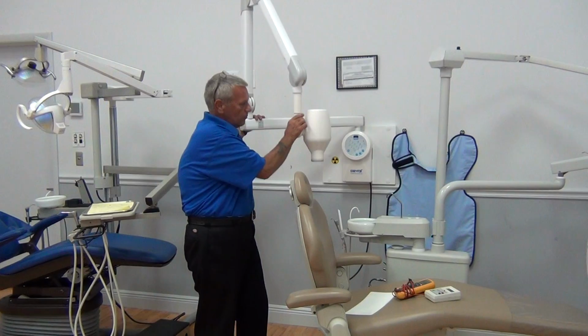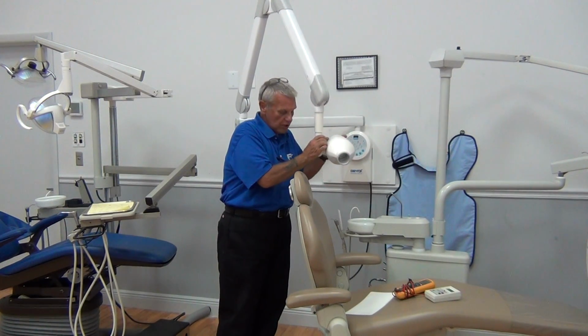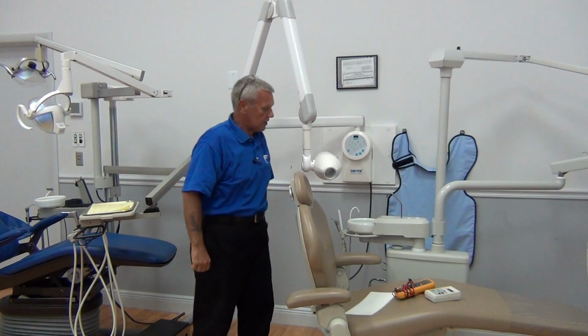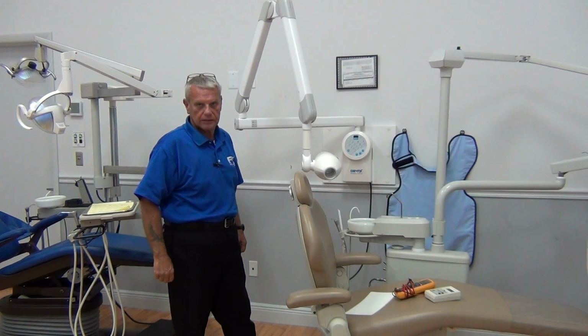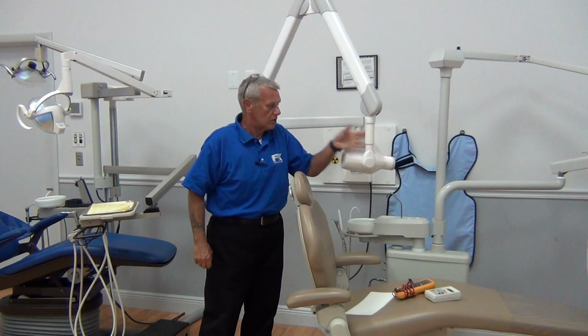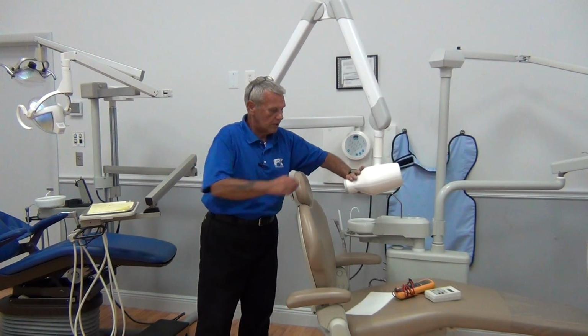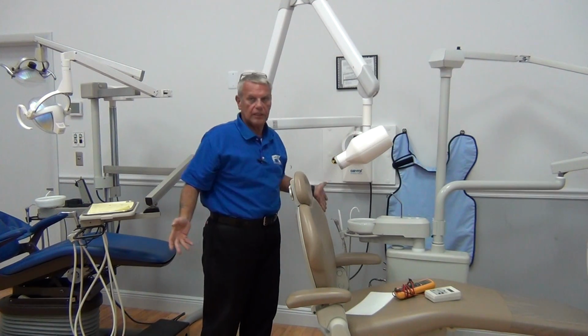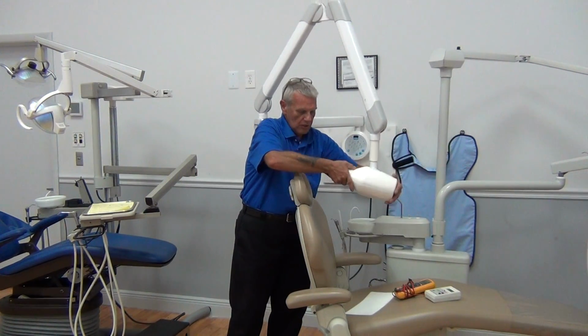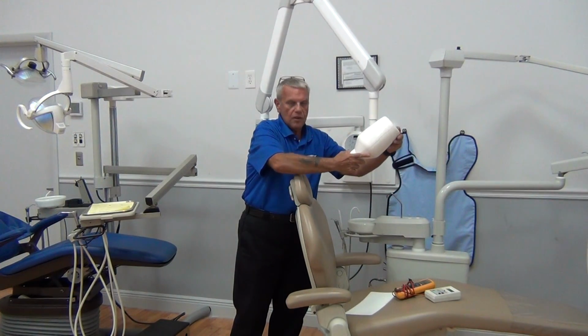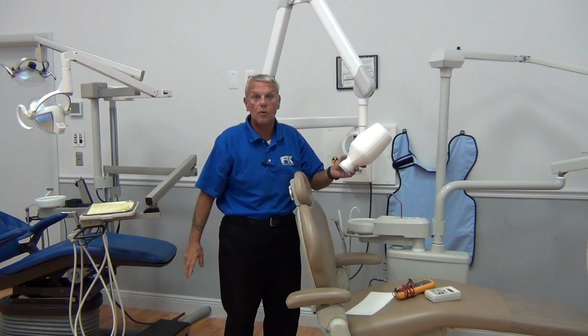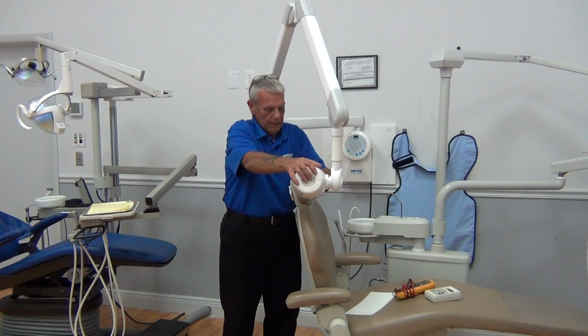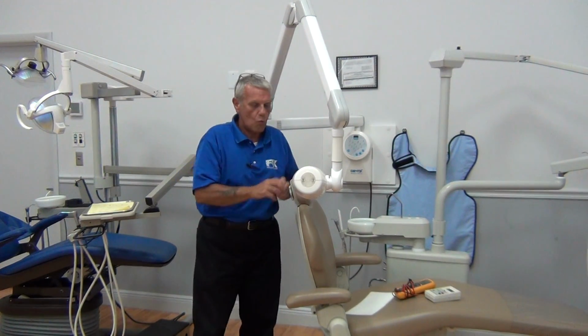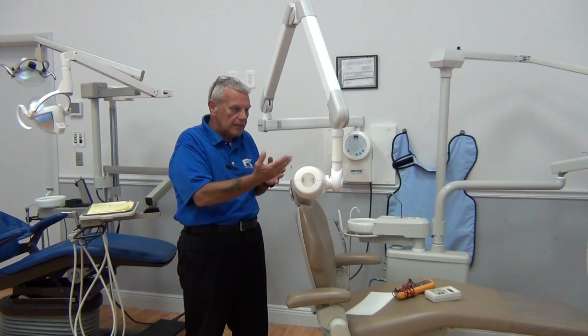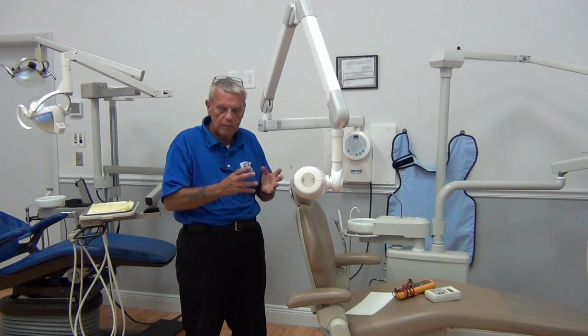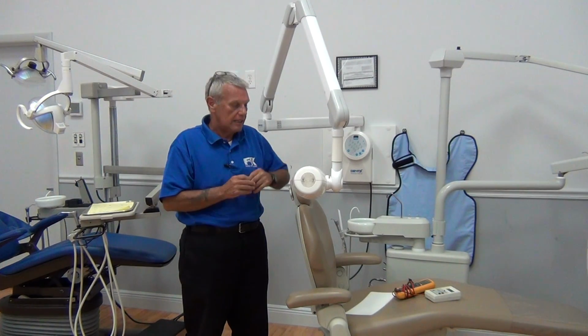Now we're going to check drifts, positioned as to a patient as if a patient were in the chair. On the left side of the patient's face, we have stability. Anterior mode, which is the front of the patient's face, we have stability. We'll check from two positions here, upward and downward from anterior. Now we're going to check our right side for stability. Ladies and gentlemen, after you're doing your stability test, wait just a second, let everything settle, and then carefully watch for movement. Any movement will be gigged by the inspector, and any movement is not acceptable.